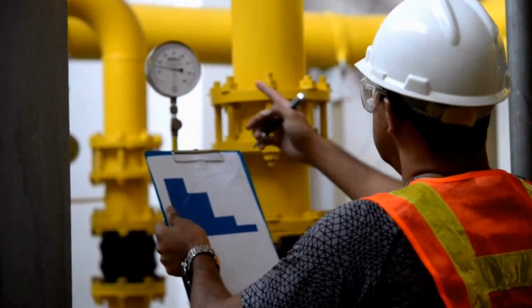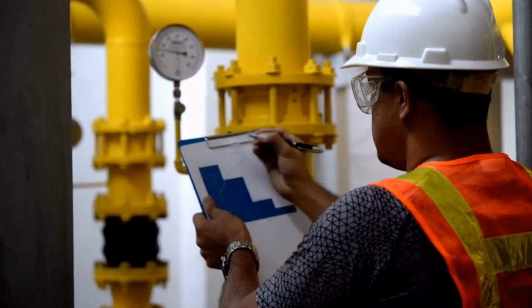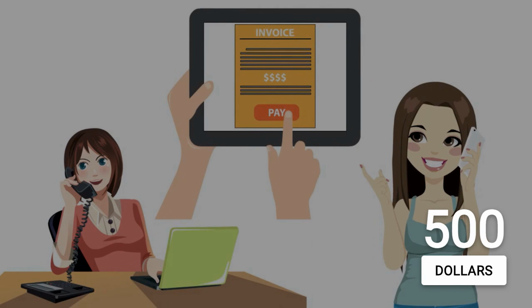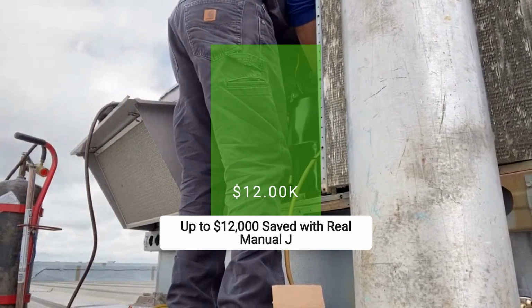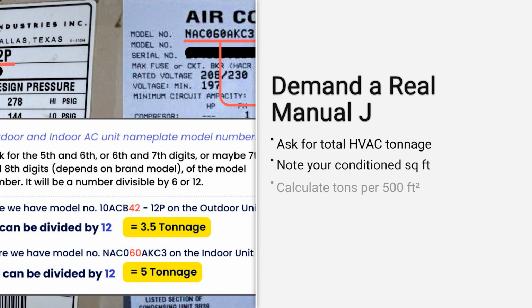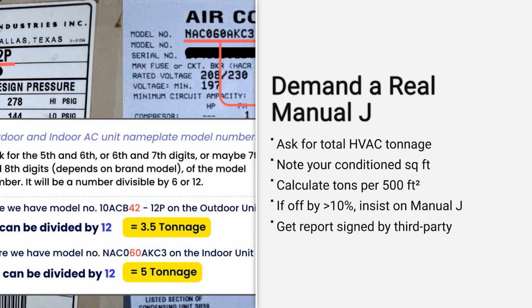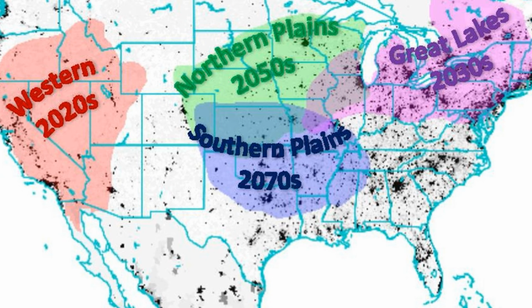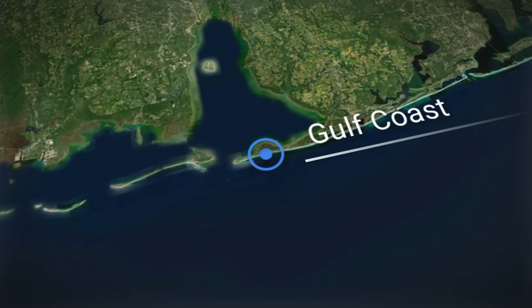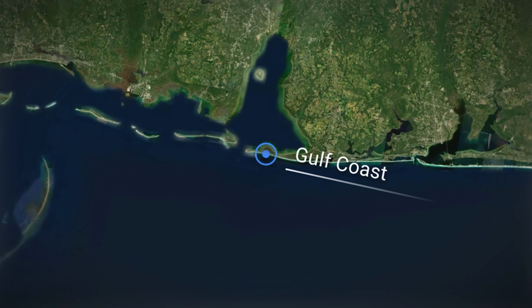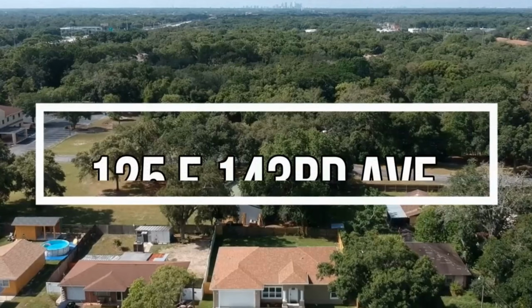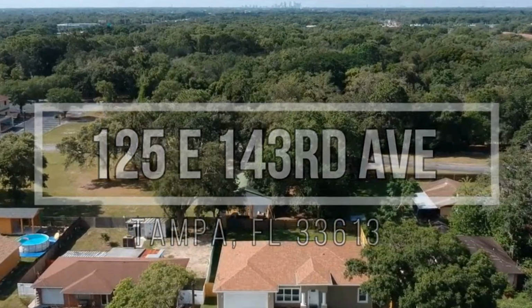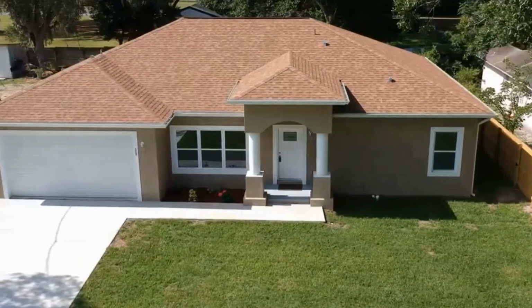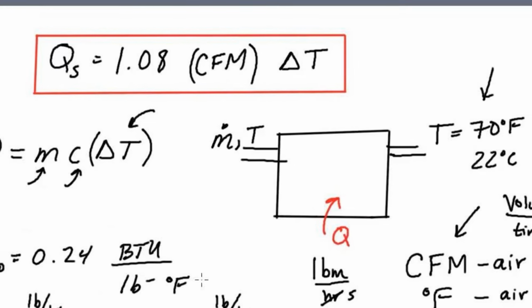Hire an independent HVAC engineer, not the builder's preferred inspector, to review the installed equipment against that calculation before closing. This service typically costs $200 to $500. The potential avoidance is $8,000 to $12,000 in premature replacement costs plus 20 years of inflated energy bills. Ask specifically for the total tonnage installed and compare it against your home's conditioned square footage, climate zone, and ceiling height. In a hot and humid climate, Florida, coastal Texas, Louisiana, the Gulf Coast, assume you need more capacity than the builder's formula provides, not less. A one-story home in Tampa with 9-foot ceilings, standard attic insulation, and west-facing windows likely needs closer to 1 ton per 400 square feet, not 1 ton per 500.